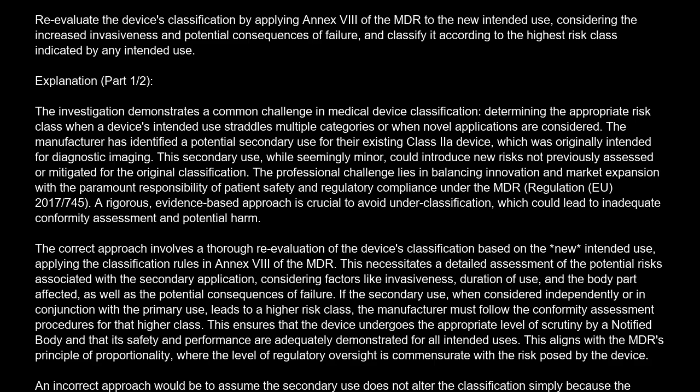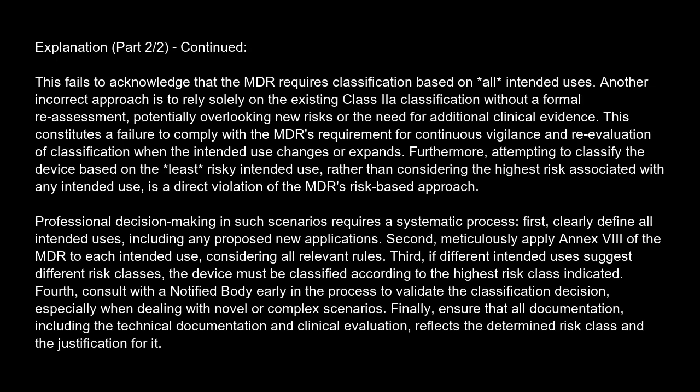by the device. An incorrect approach would be to assume the secondary use does not alter the classification simply because the primary intended use remains. This fails to acknowledge that the MDR requires classification based on all intended uses. Another incorrect approach is to rely solely on the existing Class IIa classification without a formal reassessment, potentially overlooking new risks or the need for additional clinical evidence.